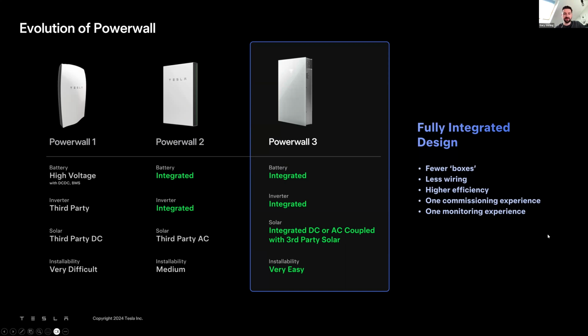Hence why we're now ready to bring out Powerwall 3. We've integrated the battery inverter and the solar inverter all into a single unit, so you're now capable of AC or DC coupling it, and you can actually do both at the same time. It's a lot easier to install. The whole front door of the unit comes off, and the whole top third of the unit is the wiring chamber, so there's tons more flexibility.